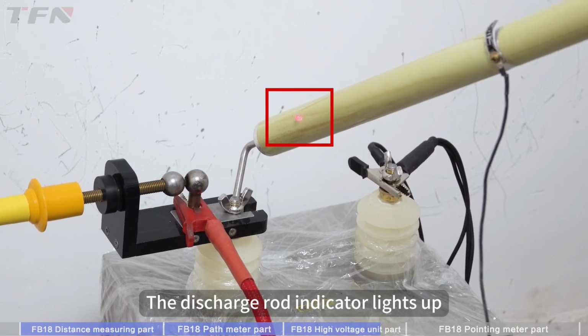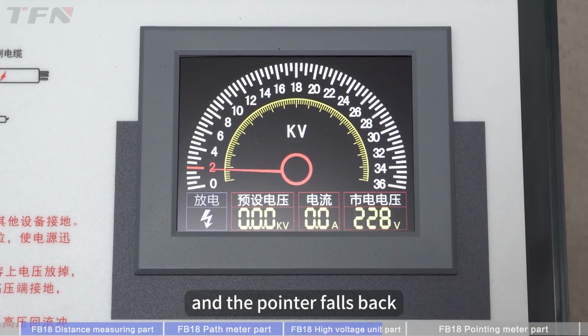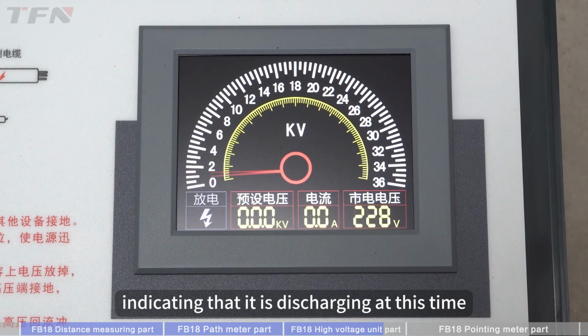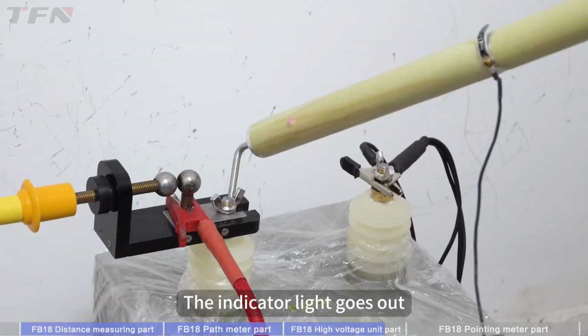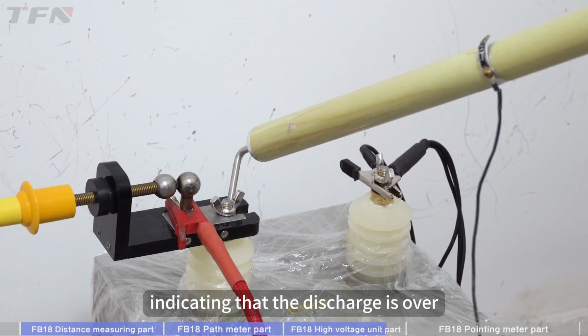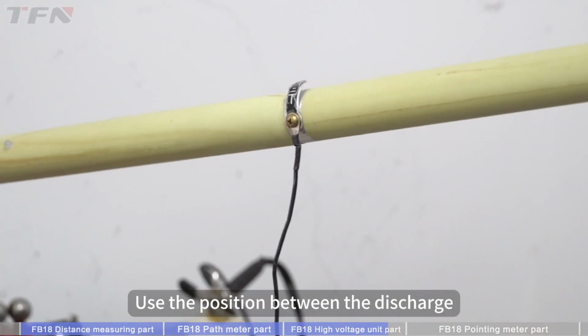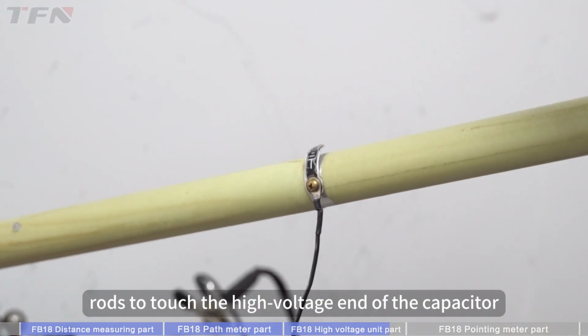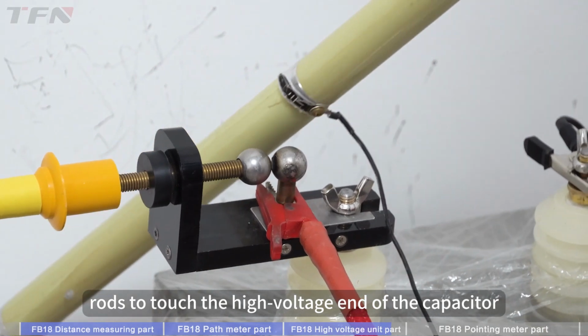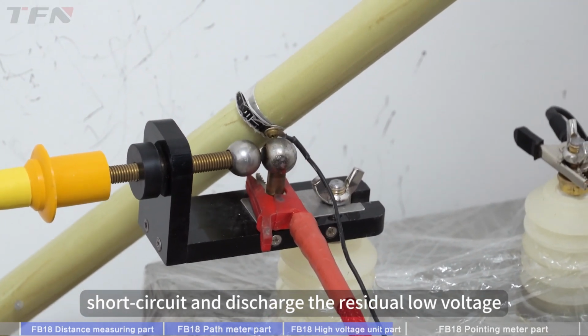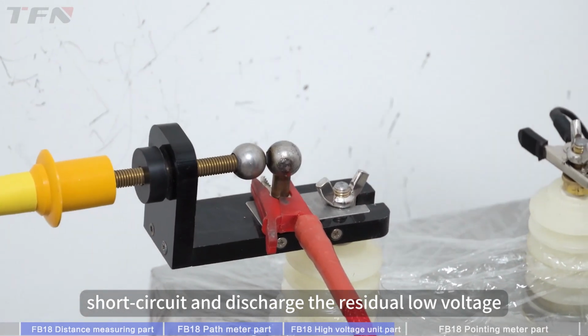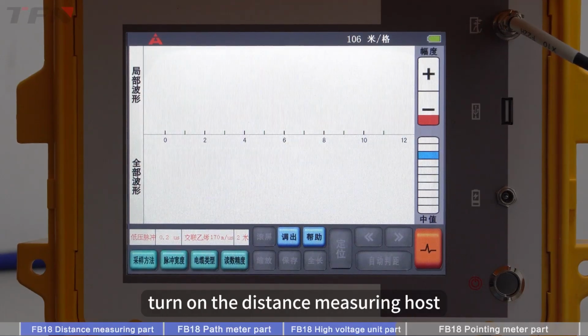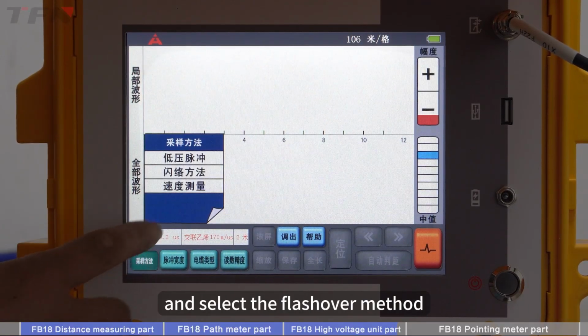The discharge rod indicator lights up and the pointer falls back, indicating that it is discharging at this time. The indicator light goes out, indicating that the discharge is over. Use the position between the discharge rods to touch the high voltage end of the capacitor, short circuit, and discharge the residual low voltage.